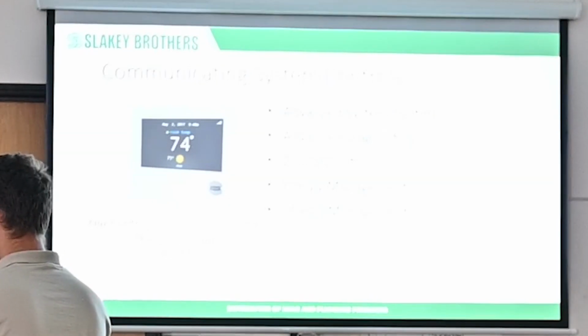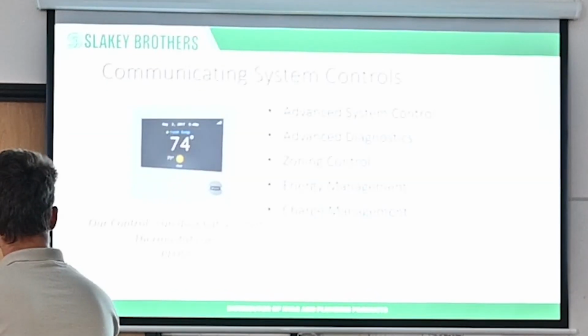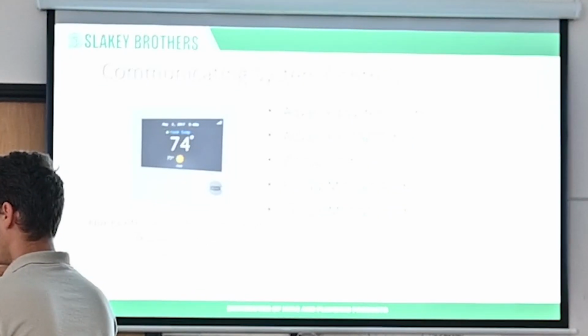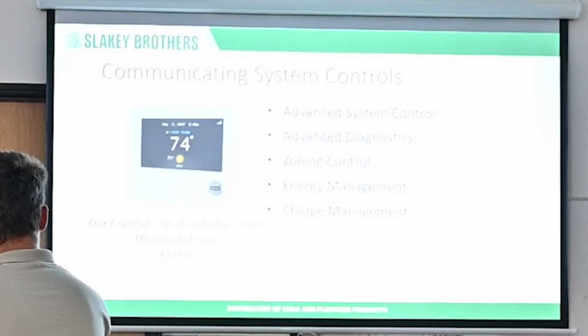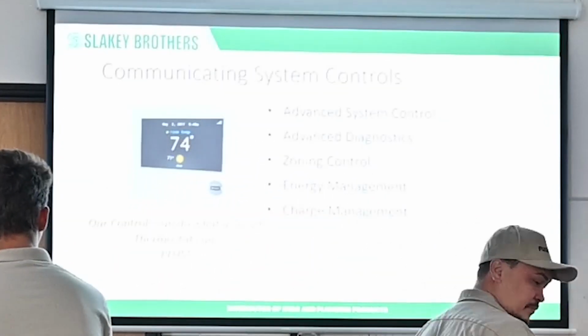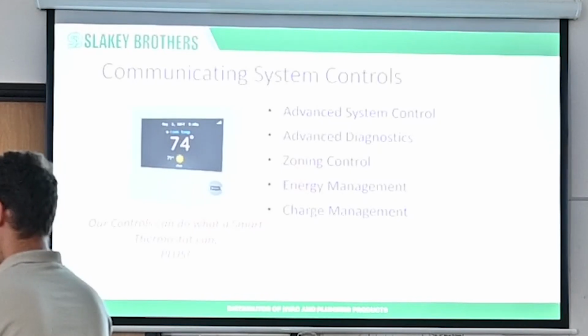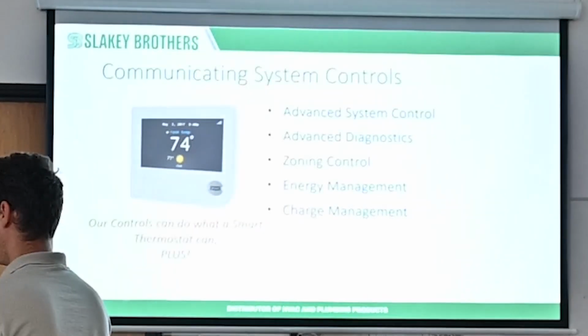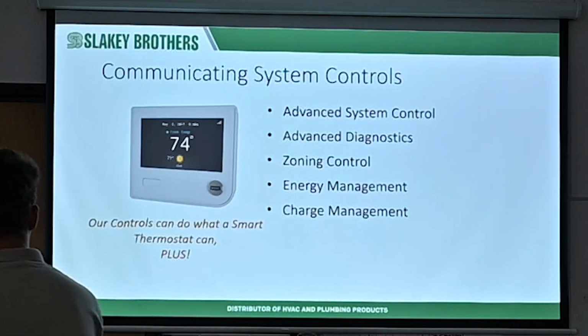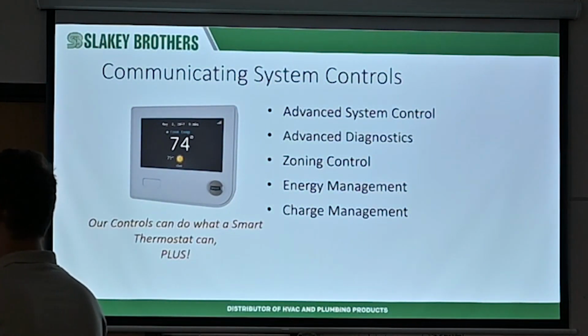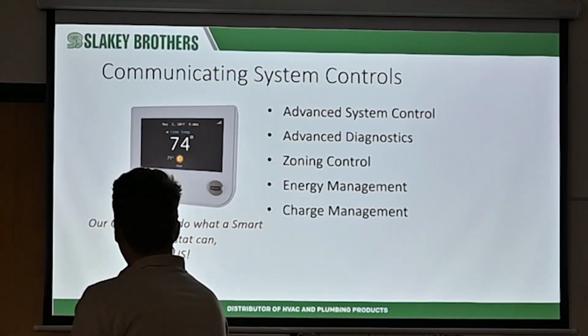It's an option because, let's say you install this in a business that has split systems already, a church or even an elderly home. Maybe you can use occupancy sensing to know that people are around. But for residential, it created a problem. They used to ship them enabled, and people were like, "Why is this thing shutting off? All of a sudden my AC doesn't work, my heater doesn't work." It's because occupancy sensing was on. So there's that feature on it, but we'll discuss all that overall. Airflow is definitely discussed, setting up the airflow.